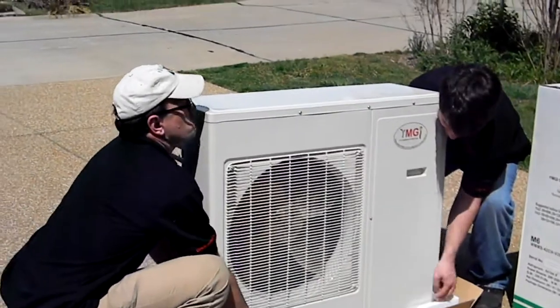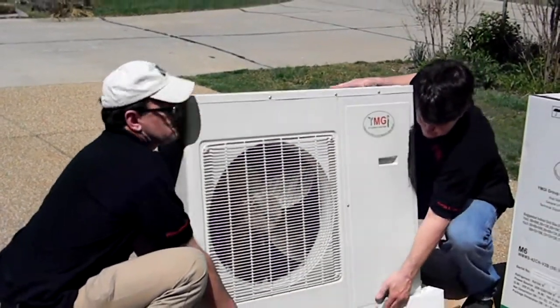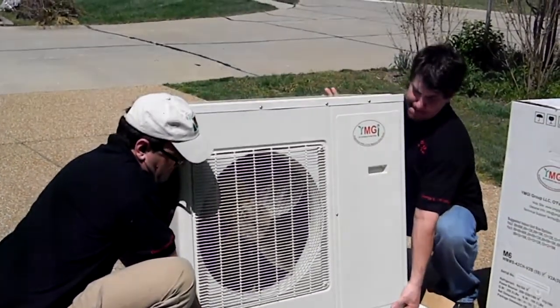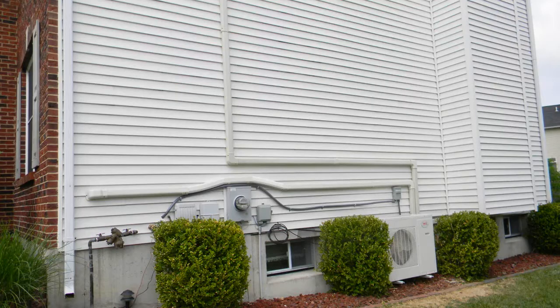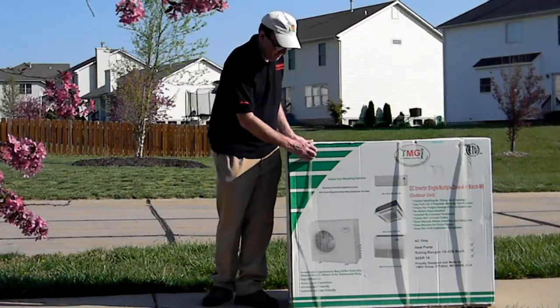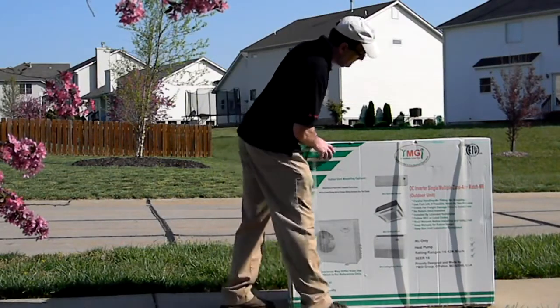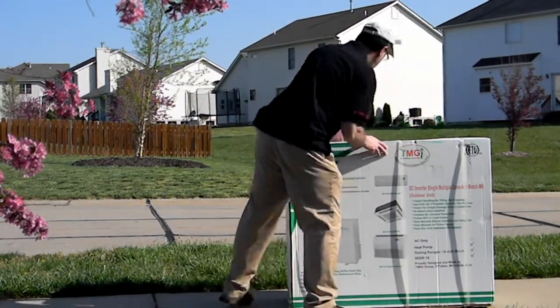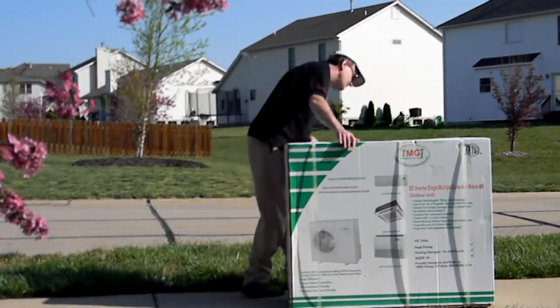YMGI strongly recommends that more than one technician be on site when installing the unit, for an easier installation and for safety reasons. In this video, we will be installing a YMGI 592 42,000 BTU 3-zone condensing unit to illustrate the recommended procedures to ensure a successful unit operation. Check for any shipping damage to the boxes when receiving your unit. If damage is found, mark it on the shipping papers with the shipper present and notify YMGI customer service immediately.